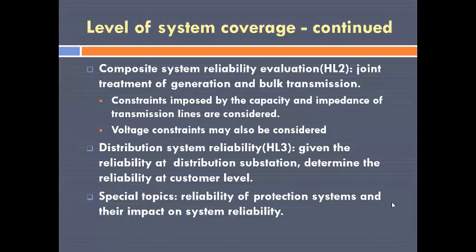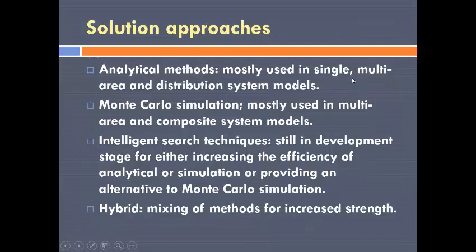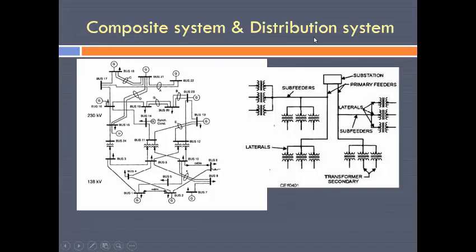The third level is the distribution system reliability. Distribution systems are connected to a substation, and the substation is fed from one of the buses of the composite system. It would be very difficult, if not impossible, to consider the distribution, transmission, and generation all together. So what we do is find the reliability indices of the substation, and knowing those indices we can then compute the reliability indices of the distribution system.